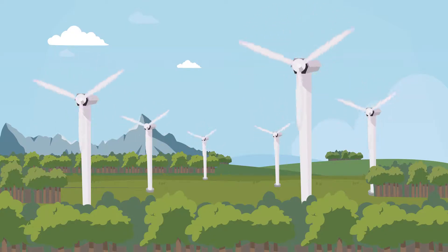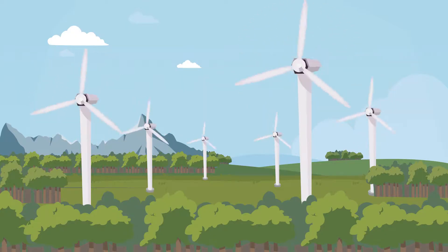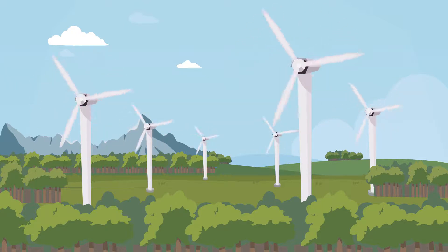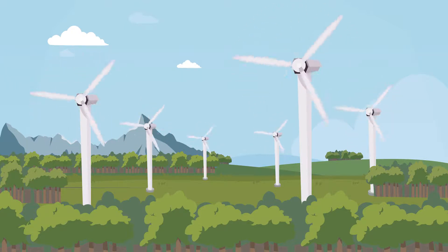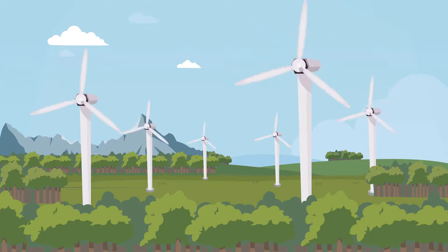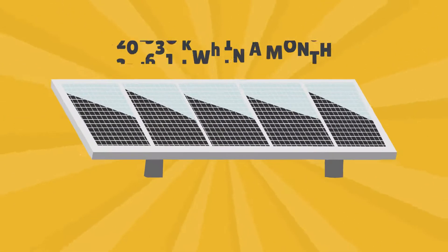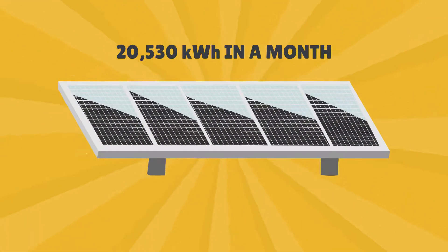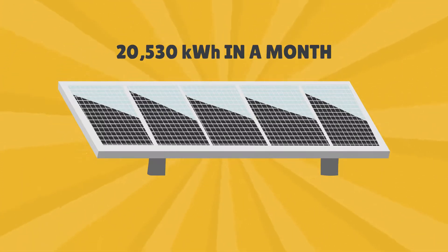Renewable energy sources such as wind and solar power can't always produce power at full nameplate capacity, since they rely on variable inputs like the wind and sun. If a 100 kW solar power system produces 20,530 kWh in a month, the capacity factor is calculated as follows.